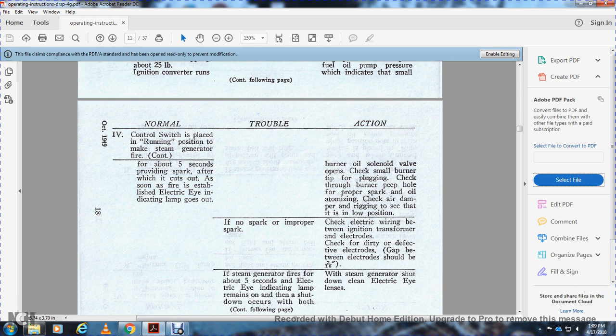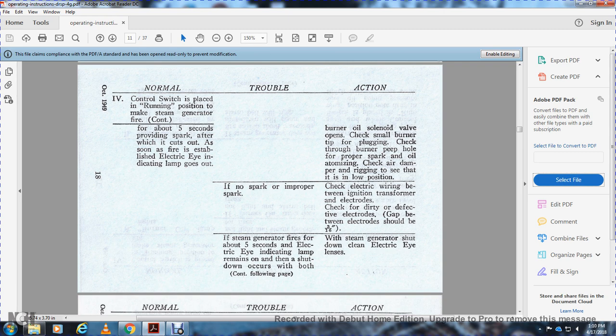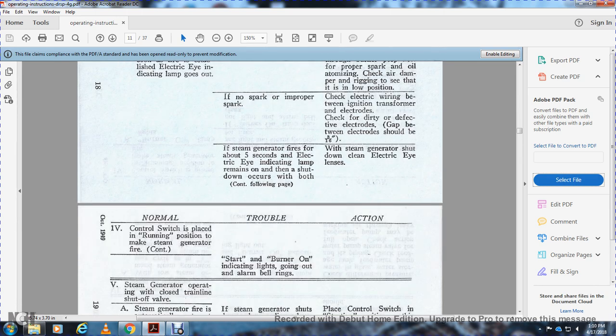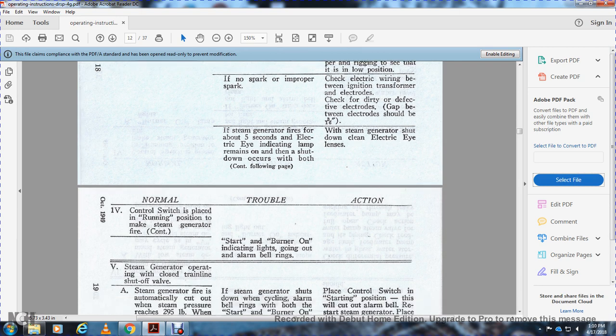Trouble, if no spark or improper spark, check the electrical wiring between the ignition transformer and electrodes. Check for defective electrodes; the gap between the electrodes should be 3/16 of an inch. If the steam generator fires but after 5 seconds the electrical eye indicating lamp remains on, the shutdown occurs with both starter and burner on indicating lights going out and the alarm bell ringing. With the steam generator shut down, clean the electrical eye and lens.